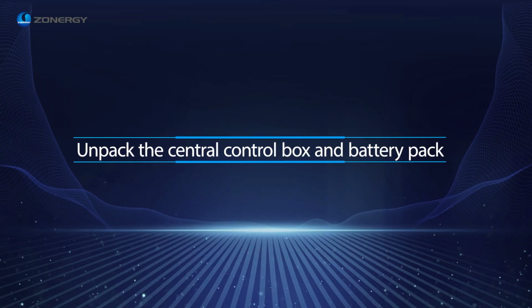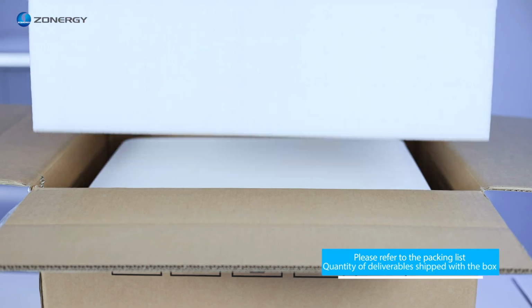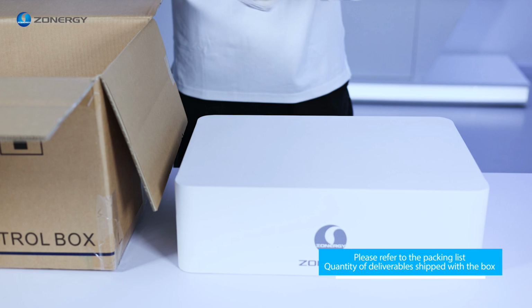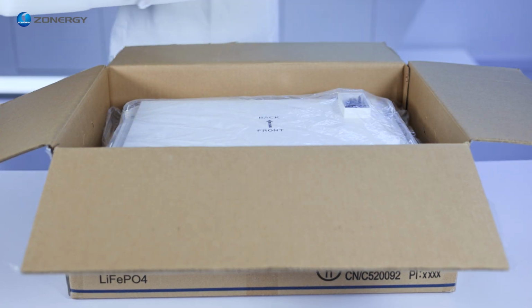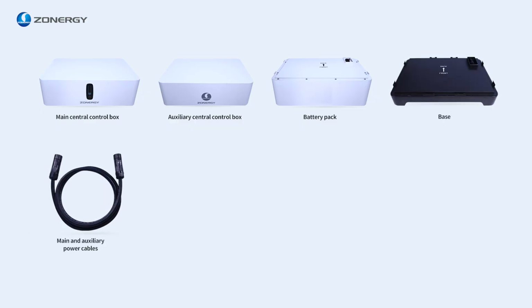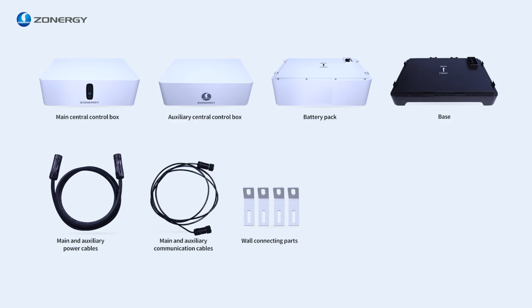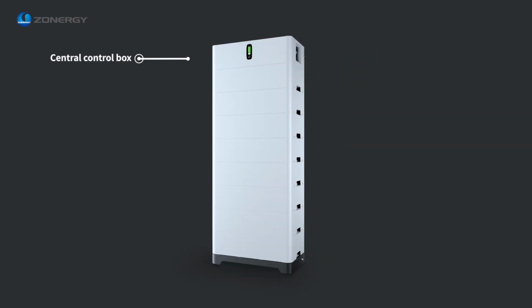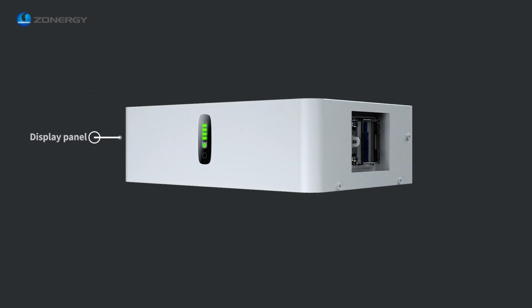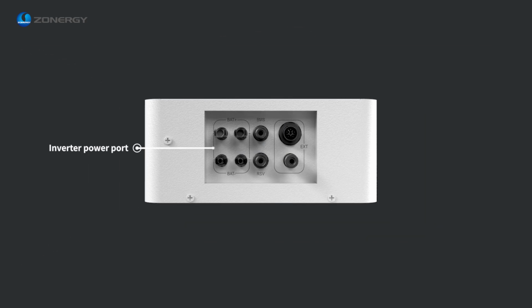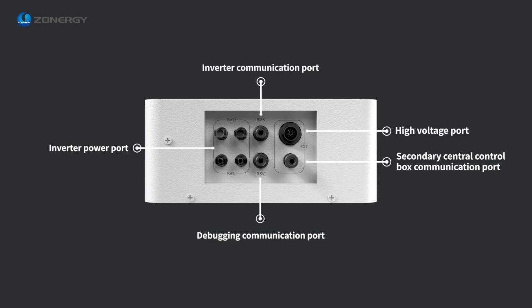Chapter 5. Unpack the central control box and battery pack. Before unpacking, check the parts and batteries with the parts list to see if any parts are damaged or missing. Products and accessories inside include as follows: main central control box, auxiliary central control box, battery pack, base, main and auxiliary power cables, main and auxiliary communication cables, wall connecting parts, self-tapping screws, expansion tubes, stainless steel combination screws, 5-core short wiring. The battery appearance and ports are as follows: central control box, battery pack, base, display panel, circuit breaker, inverter power port, inverter communication port, debugging communication port, high voltage port, secondary central control box communication port.